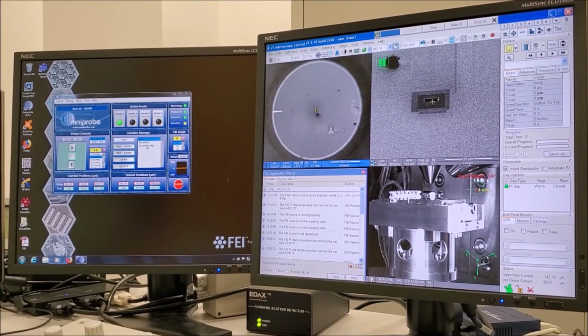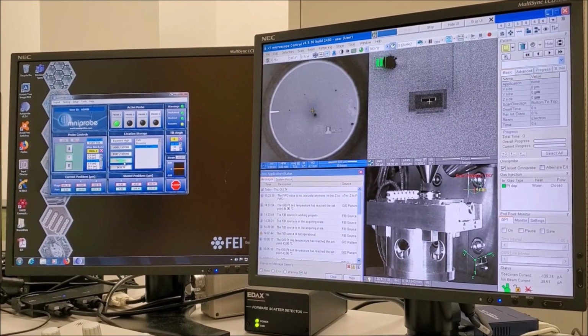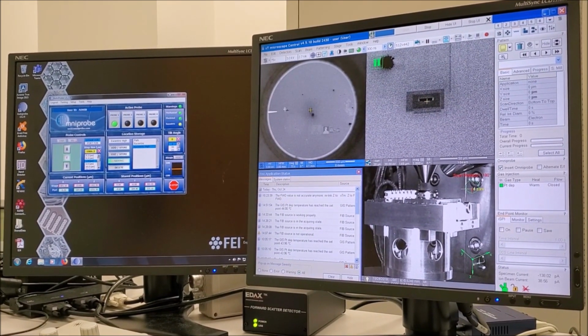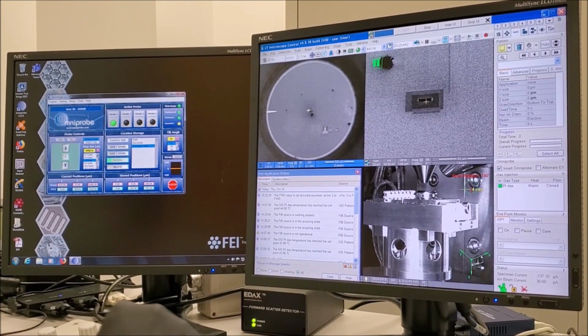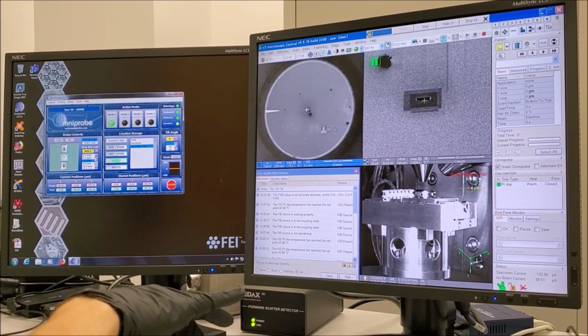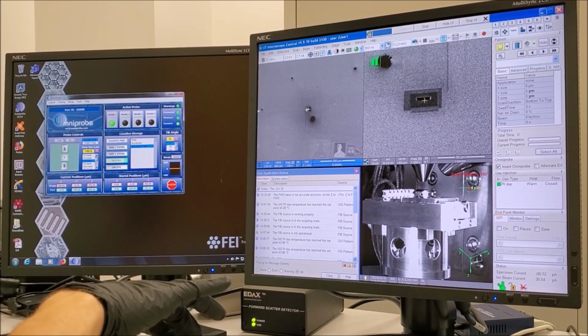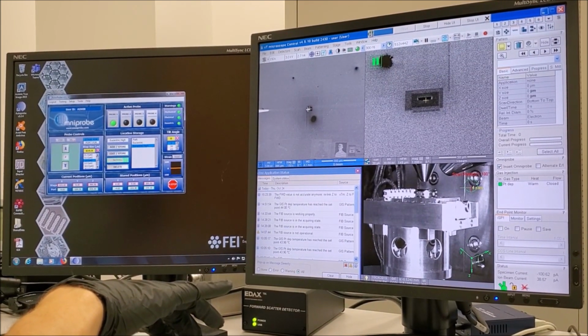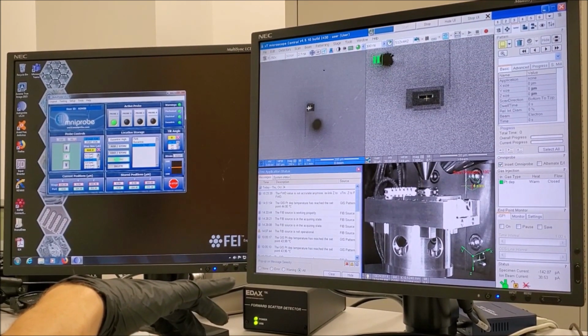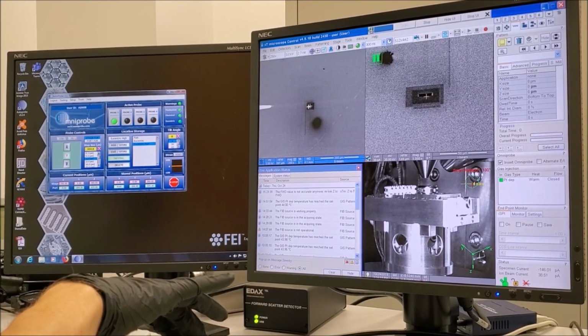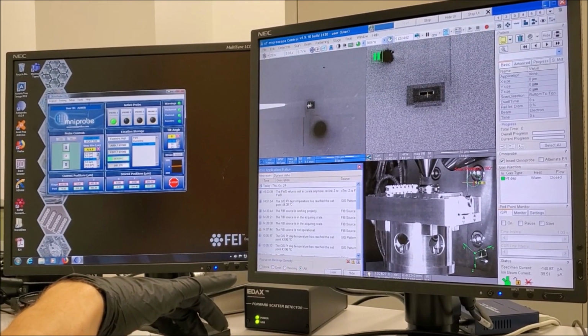Using the AutoProbe software on the second monitor, under Location Storage, select Eccentric High and then Go To. This moves the OmniProbe to directly over the center of the image, approximately 300 microns above the sample surface. When the OmniProbe has reached the eccentric high position, it can be brought down to the sample surface.